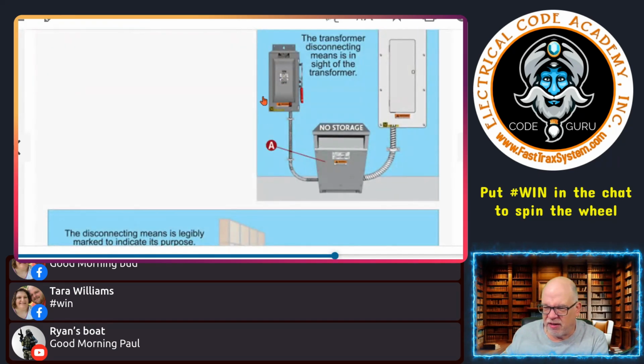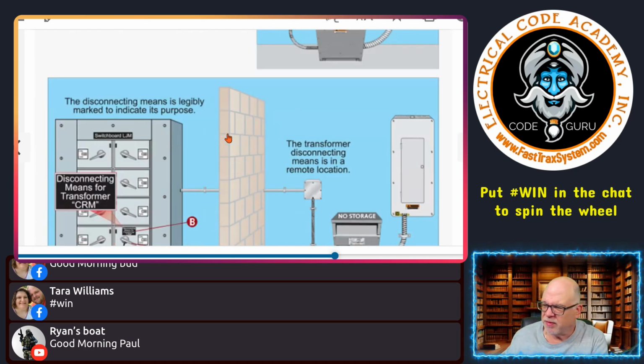In this case right here, I am sure there are fuses in there. So it is a disconnect, but it's also probably sized for the primary protection for the primary conductors, and it probably also provides the 450.3 protection for the transformer, all in there. But remember, we're just talking disconnect at this point. That's all we were really talking about, that function, if you will.